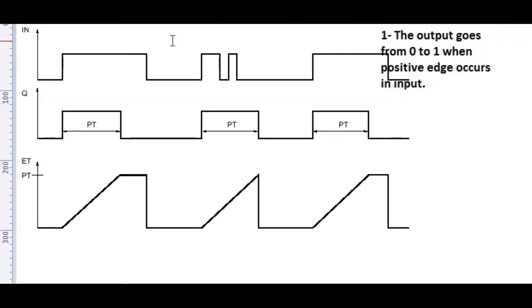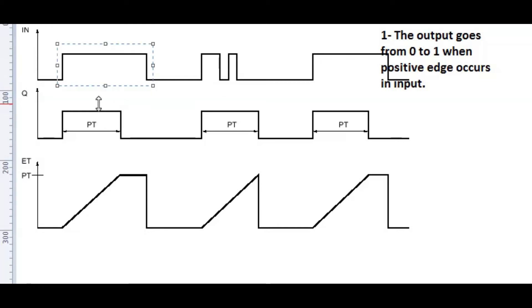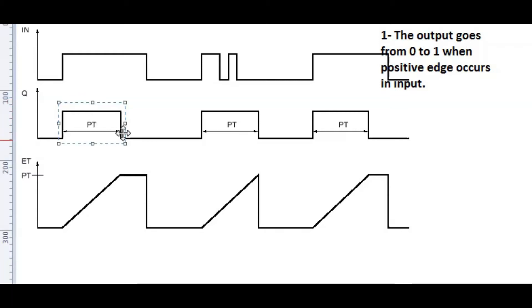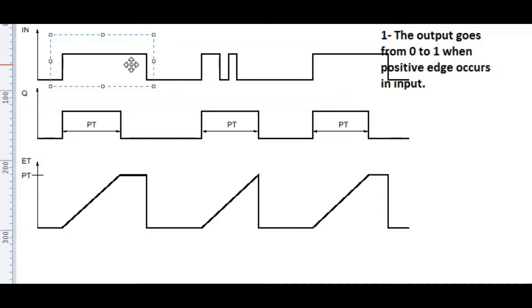Now let's see the second working principle. As you can see from the graph, the input is still high but the output goes to 0. This means when the timer completes — let's say we have set the timer for 10 seconds and those 10 seconds finish — the output goes to 0, even if the input is still high. That means the output is independent of the input and depends on the timer.